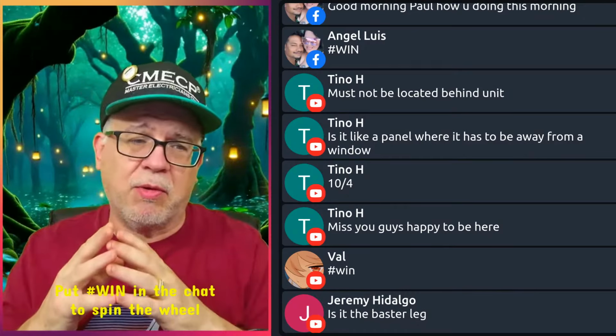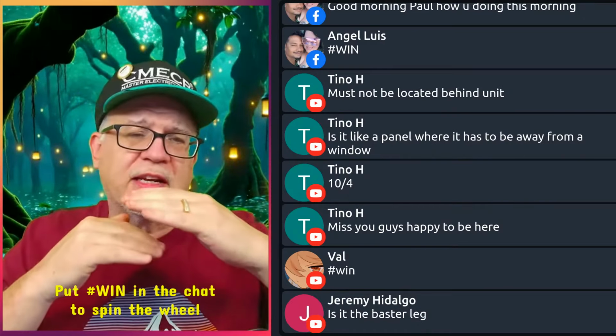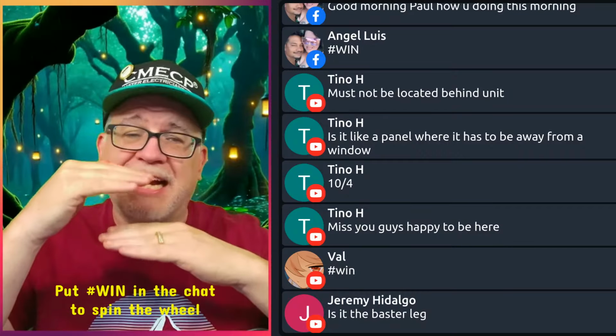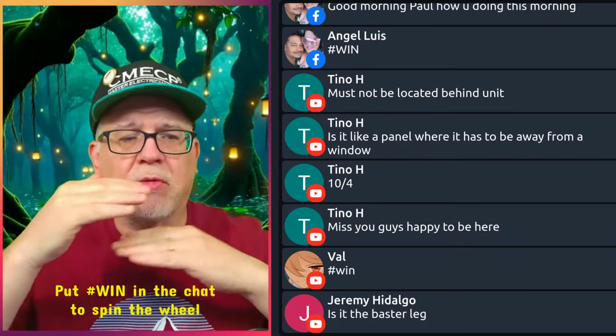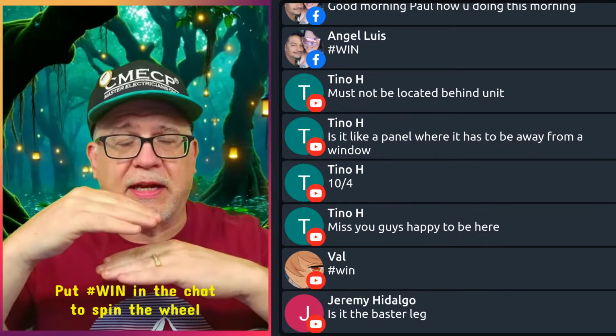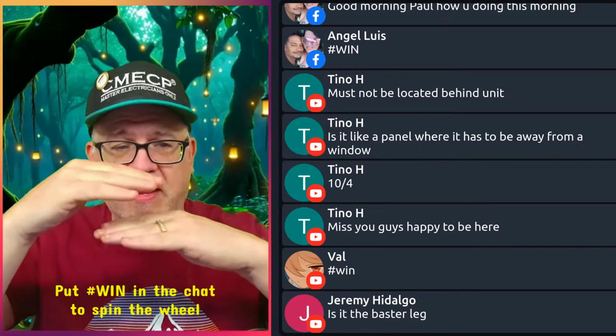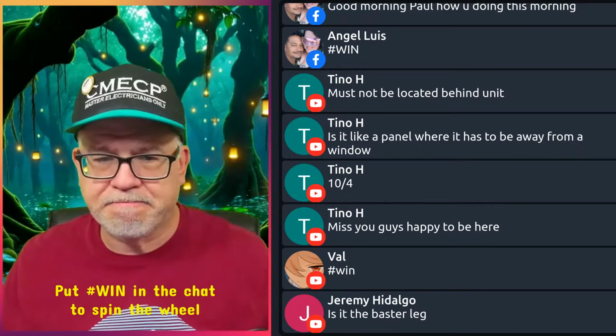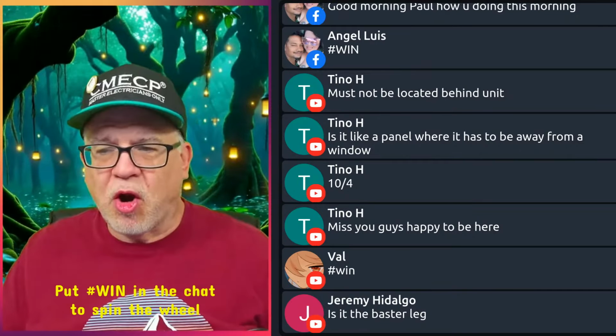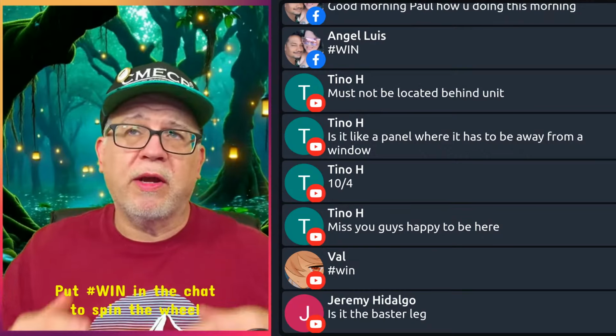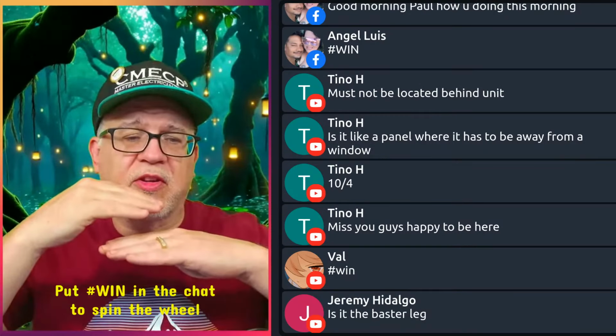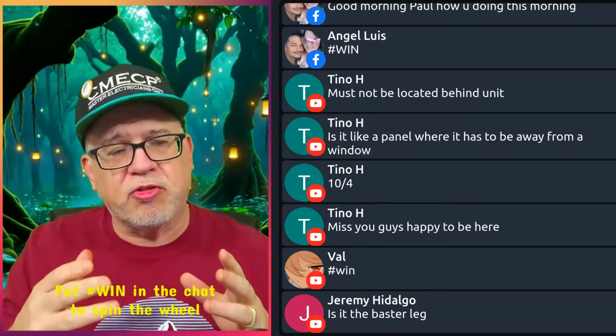But you have some allowances in the code when you're doing selective coordination. If both pieces of equipment are identical, then you don't necessarily have to selectively coordinate them, because they're identical. They're going to be at the same levels. That type of thing. A smart, practical design will always try to design a system, again, so it clears closest to the incident.